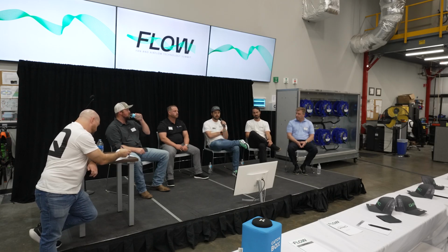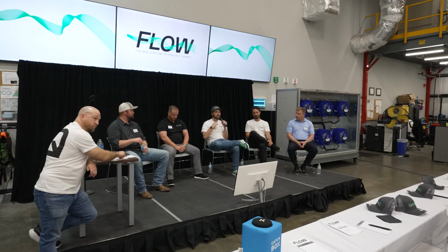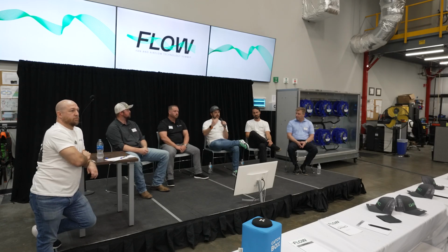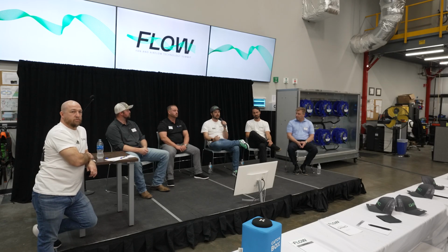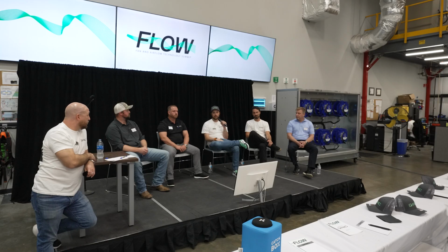Even if something were to fail, any component inside that board were to fail, the 0 to 10 volt signal you're sending would bypass all the electronics, bypass all the brains and everything, and still make it out to the motors.